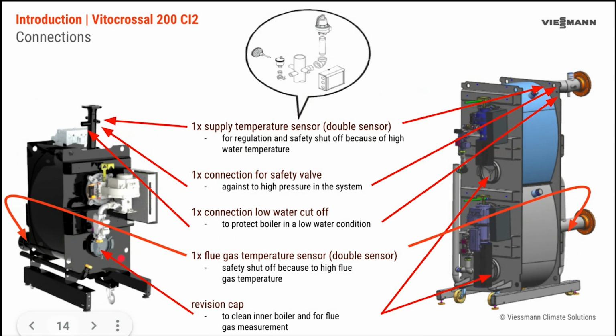The revision cap, one here on the face of the boiler for singles and two on the double deckers, is actually twofold in its use. We'll use this in our annual service to access the heat exchanger for cleaning. And additionally, we'll do our combustion testing here. That may seem slightly unusual, as we would typically test combustion in the flue.